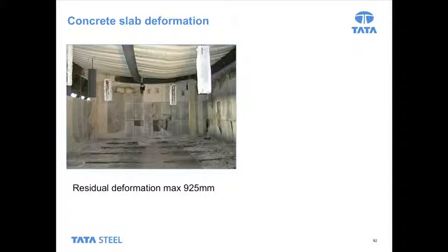This is kind of a picture of the compartment below. So some fairly major deflections here, a total deflection of 925 millimeters in the worst position. But because there was no collapse, the test proved that the Broadgate fire, which happened during construction, wasn't a fluke.